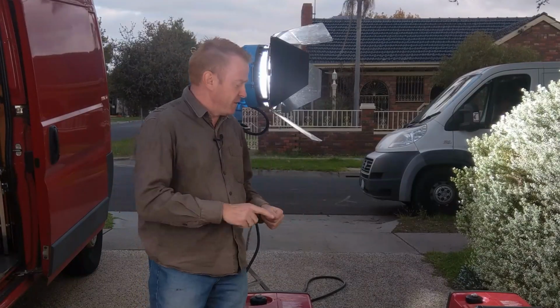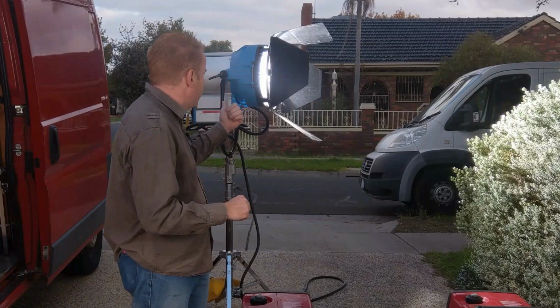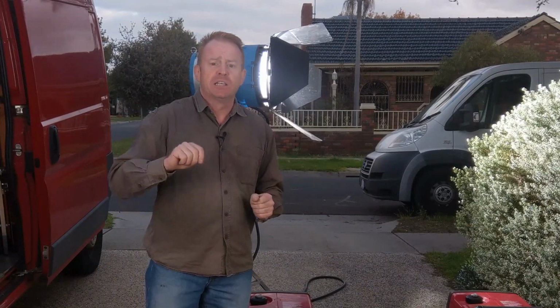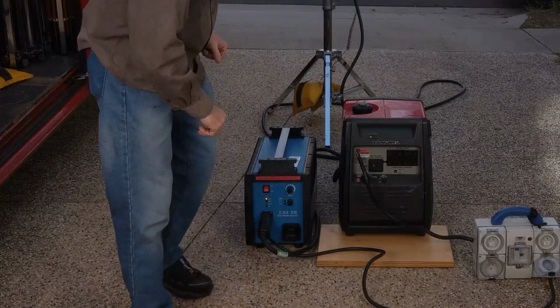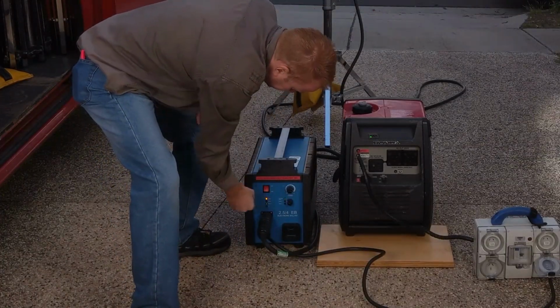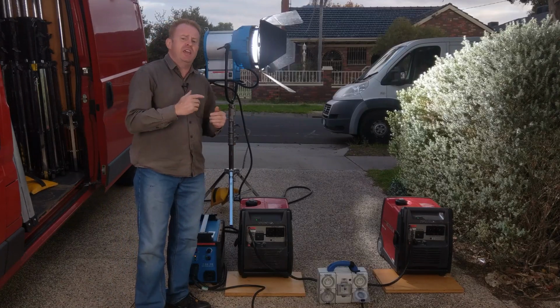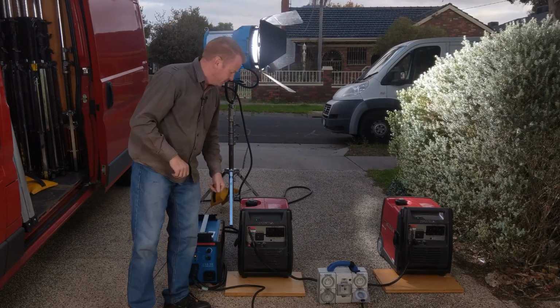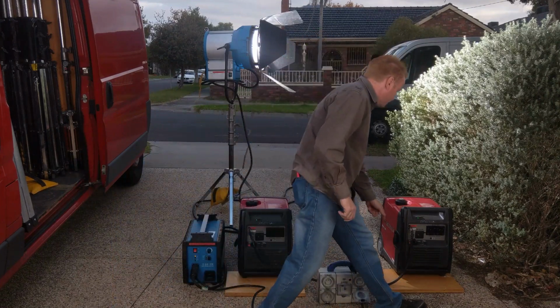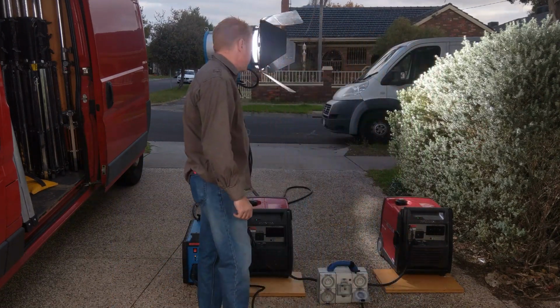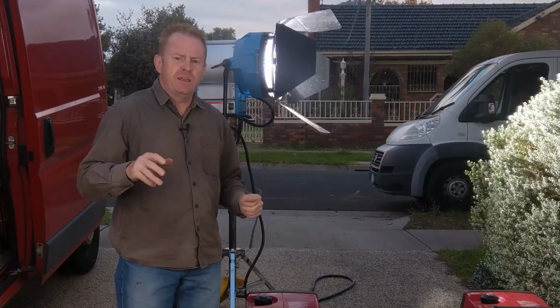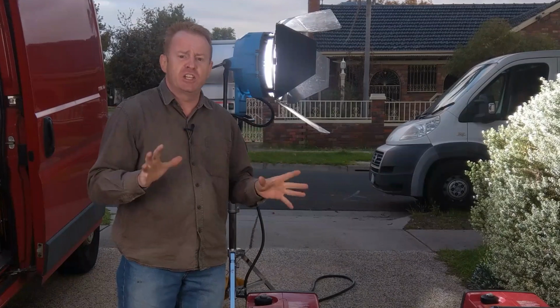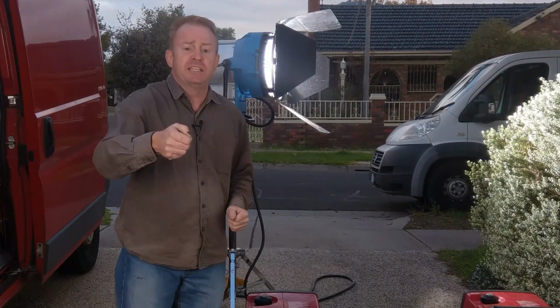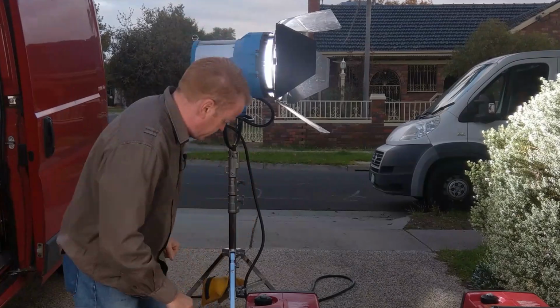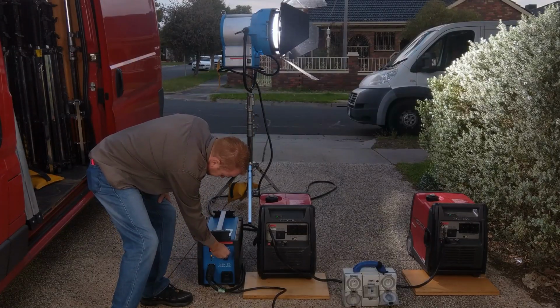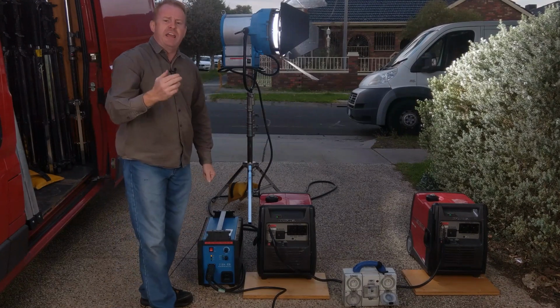Now I know from testing that these generators won't be able to take the load of this HMI at full power, so I have to dim it down a little bit. And now I can turn the eco throttles back on and save a bit of fuel. Now, if you've got two generators linked together and you're going to turn off a big load like this, I would suggest dimming the HMI all the way down first, and then flicking the breaker.